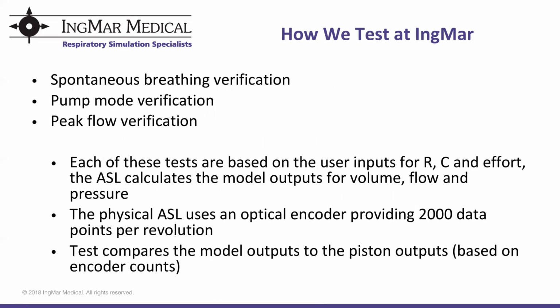I combined the next 3 tests into a single slide because we use the same evaluation methodology to verify these tests. The 3 tests are spontaneous breathing verification, pump mode verification, and peak flow verification. Each test evaluates a model with a resistance, a compliance, and an effort. That model is then compared to the physical position of our piston, which is measured through an optical encoder. In the end, we want to minimize the amount of error between the model and the actual data.